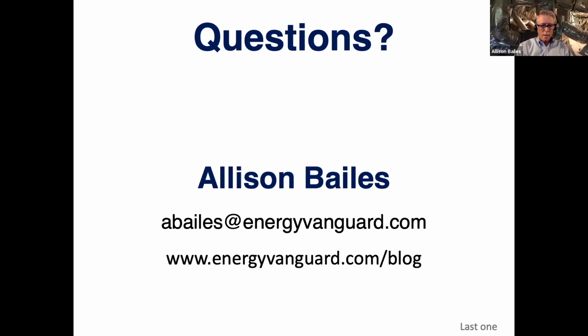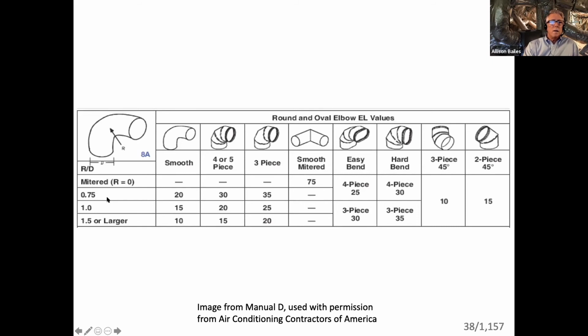So let me go back to those Manual D equivalent lengths. Here you can see that 0.75, 1, and 1.5 are the three ratios they give in this table. The bigger the radius of curvature is relative to the diameter of the duct, the lower the equivalent length. So when I was designing the big radius elbow for our office, I used 1.